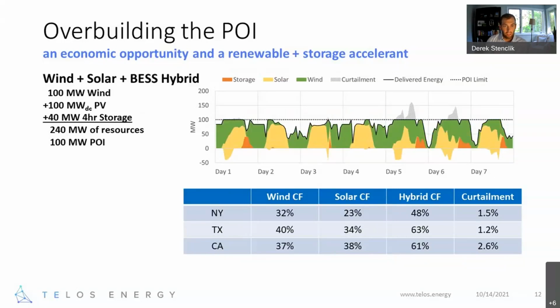And then lastly, you start combining 3 resources - now 100 megawatts of wind, 100 megawatts of solar, and 40 megawatts of storage. Again you can really see the capacity factor of the plant. We want to think of these hybrids as a plant using that 100 megawatt POI exceeding 60% with very, very little curtailment. So a lot of opportunity there.